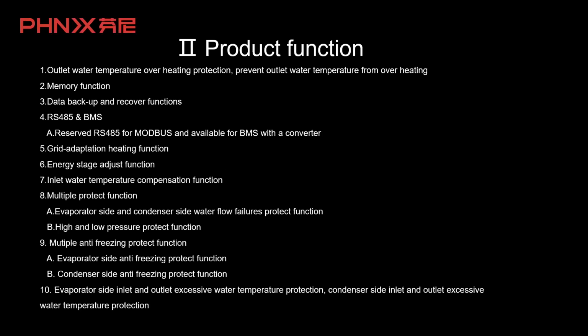It's about product functions. Number 1, outlet water temperature overheating protection, which prevents outlet water temperature from overheating. Number 2, memory function. Number 3, data backup and recover functions. So Troy, can you explain this point for me? Yes. Data backup and recover means that when the first operation at the project site is done, every parameter will be saved in the display. If the PCB, I mean the main controller, has some issue and needs to be replaced with a new one, all parameters saved in the display can match the new PCB. That's the data backup and recover function.